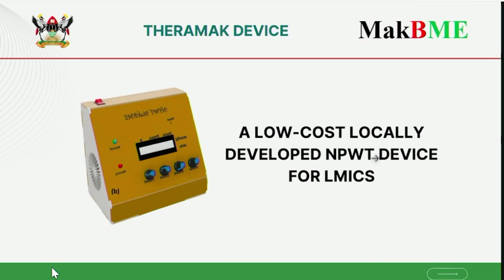So TheraMak basically comprises a microcontroller that contains the control algorithm. It also has a display screen. It has a suction pump that provides the negative pressure, and then the pressure sensor that works in sync with an alarm system for feedback. All of that is housed inside the custom acrylic casing. And this device can actually operate on power from the mains or battery, and it is also solar compatible.